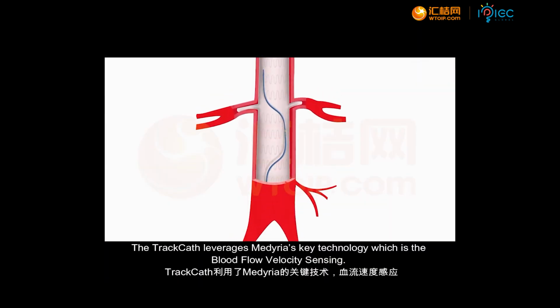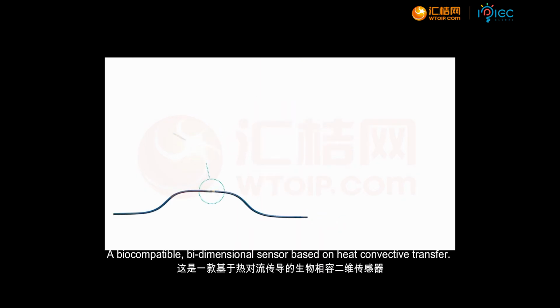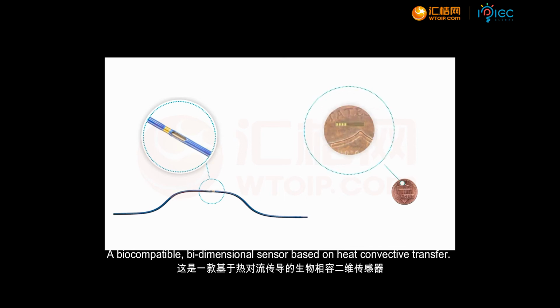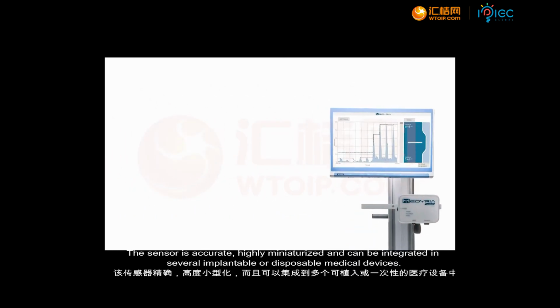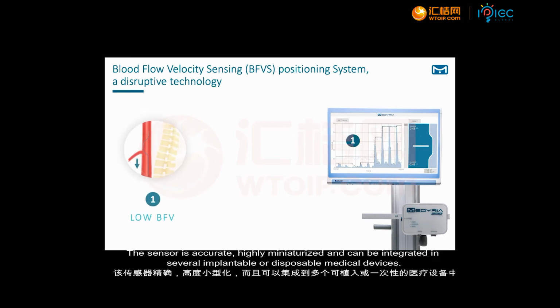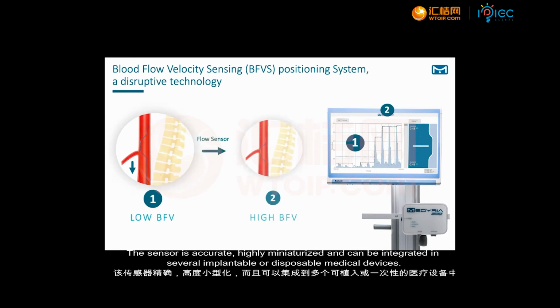TrackCath leverages Medyria's key technology, which is blood flow velocity sensing—a biocompatible, bidimensional sensor based on heat convective transfer. The sensor is accurate, highly miniaturized, and can be integrated into several implantable or disposable medical devices.